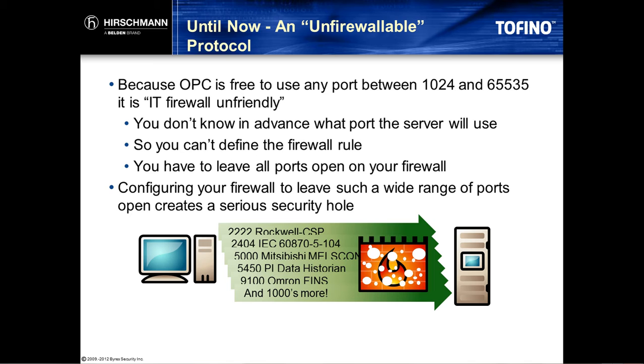65,535. A conventional firewall is basically not useful to protect an OPC server, because we don't know what port number will be used for these data connections, so we basically have to open all the ports between the client and server. And if we're opening that many ports, really, what's the point of using a firewall at all? And that's the main reason why OPC servers today usually run wide open with no firewall. So Tofino OPC Enforcer is the first security product that solves this problem in a way that's effective for use on the plant floor.